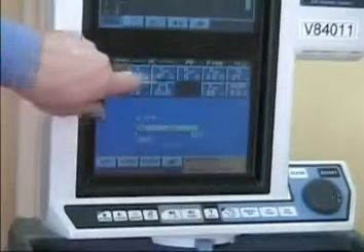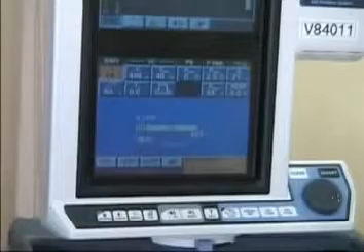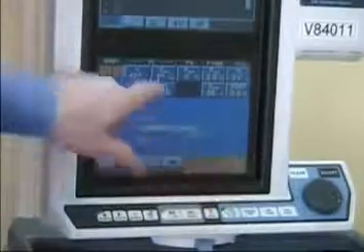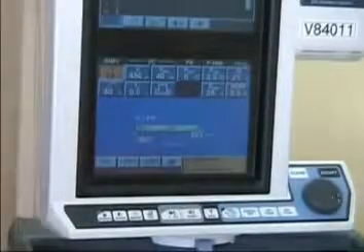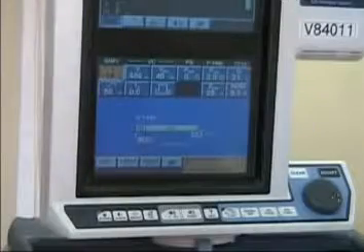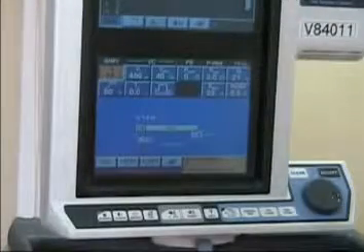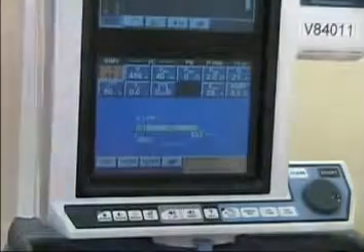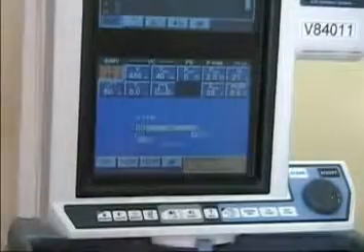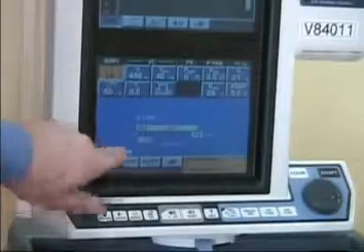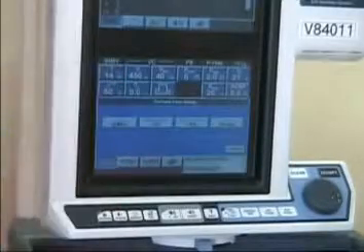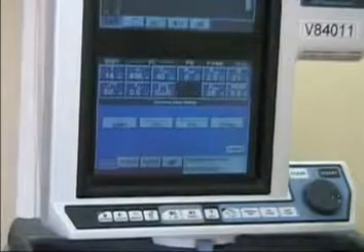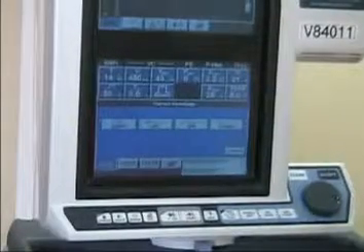If you want to change any of the parameters, you simply touch on it, change it with the rotation knob, hit accept. From this point on, the patient should be doing well enough to continue ventilation without your presence. That's why you have the alarm limits to watch over the patient while you're not available.